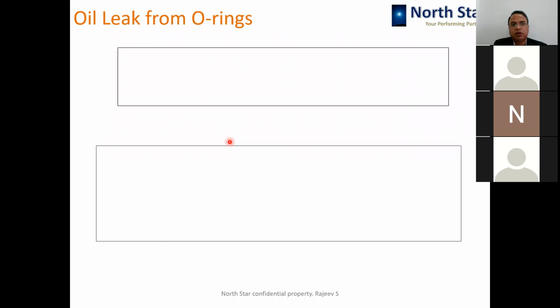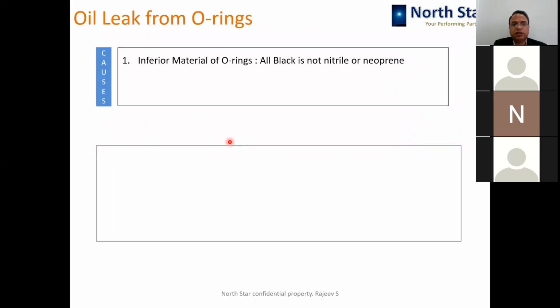Oil leakage from O-rings - one cause is that all black is not nitrile, especially when metal parts and O-rings are supplied together by the metal part supplier, which are normally not of good quality. It is better to purchase the O-ring separately and the metal part separately so that you are sure what you are purchasing and what you are putting. All black is not nitrile or neoprene.